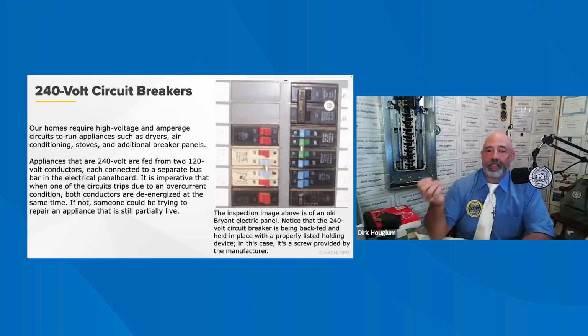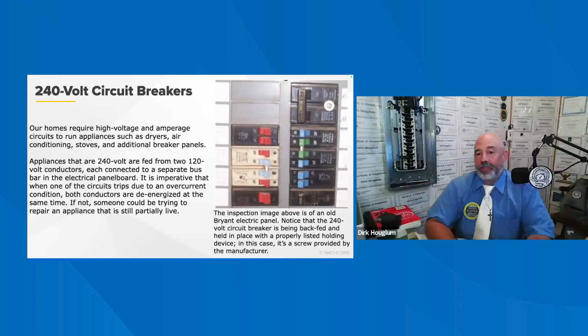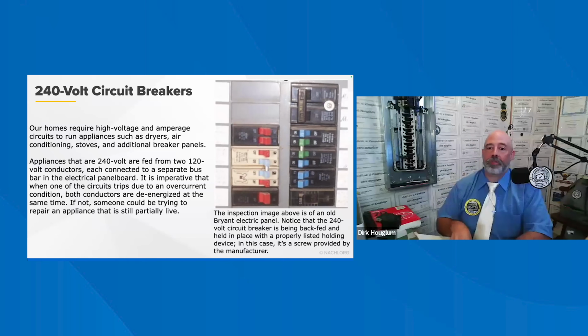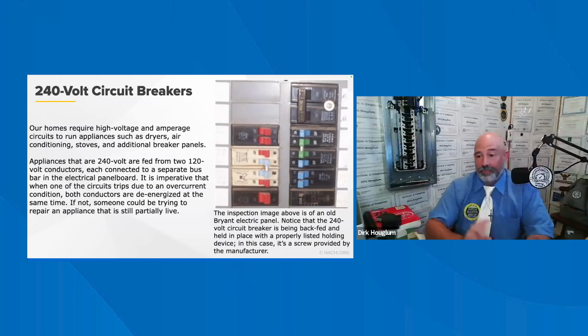The breakers are molded with this connection in place, and sometimes they are linked by a listed handle tie. The inspector should ensure that the tie is present and has not been damaged. The 240-volt circuit breaker also acts as the main disconnect means in modern panels, disconnecting all electrical power. Common 120-volt circuits are fed from the bus bar only. Also in use are tandem breakers, which are 120-volt breakers that feed two separate circuits, each controlled by its own handle. These should not be linked. As with fuses, the inspector should check that the rating of the breaker does not exceed the conductor size.